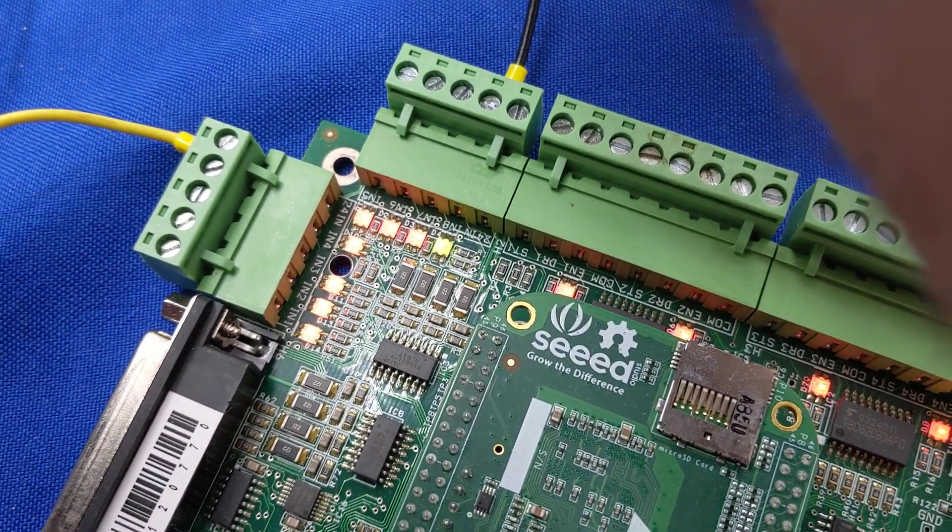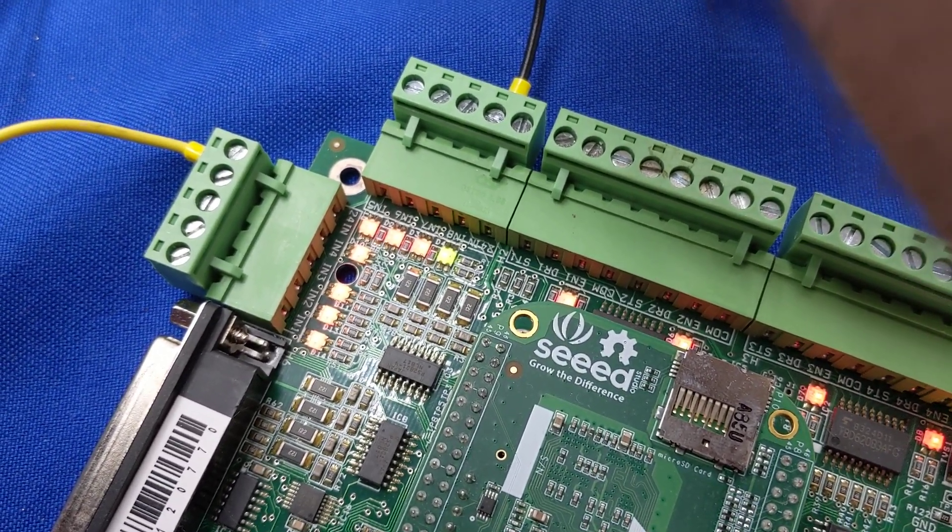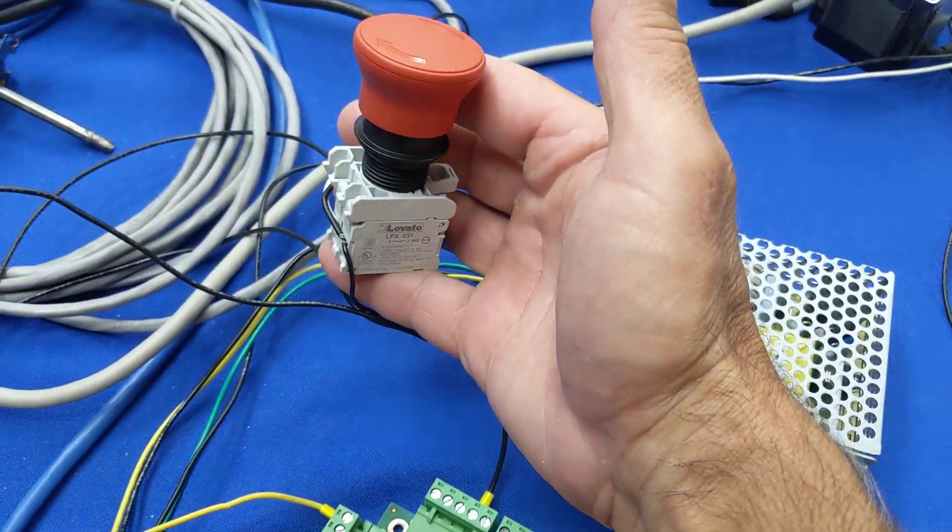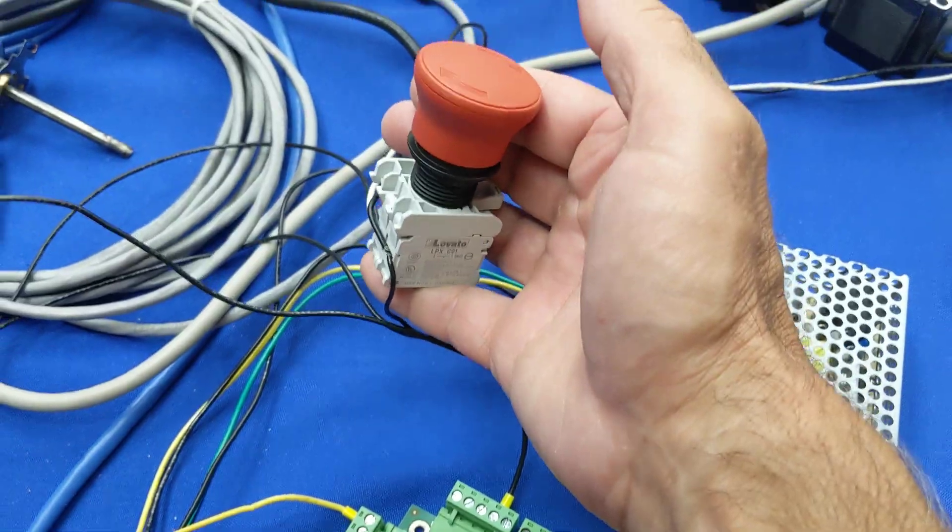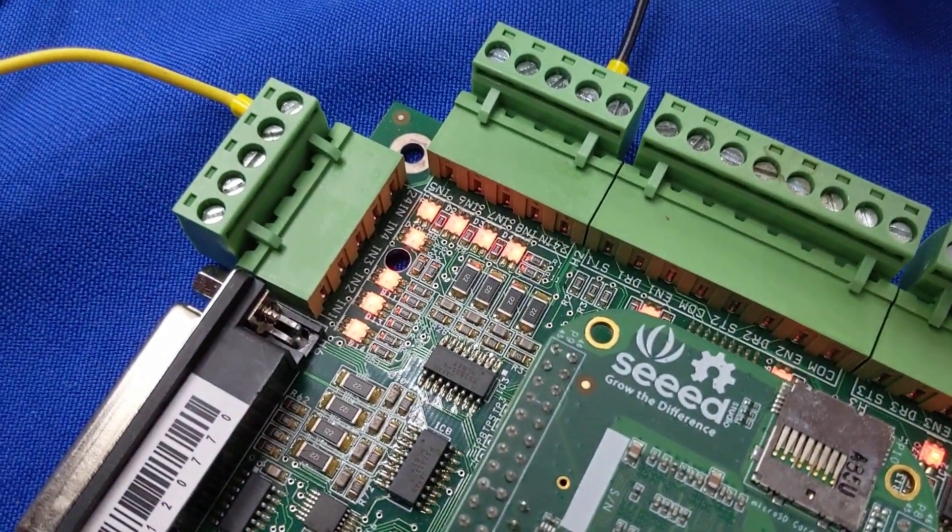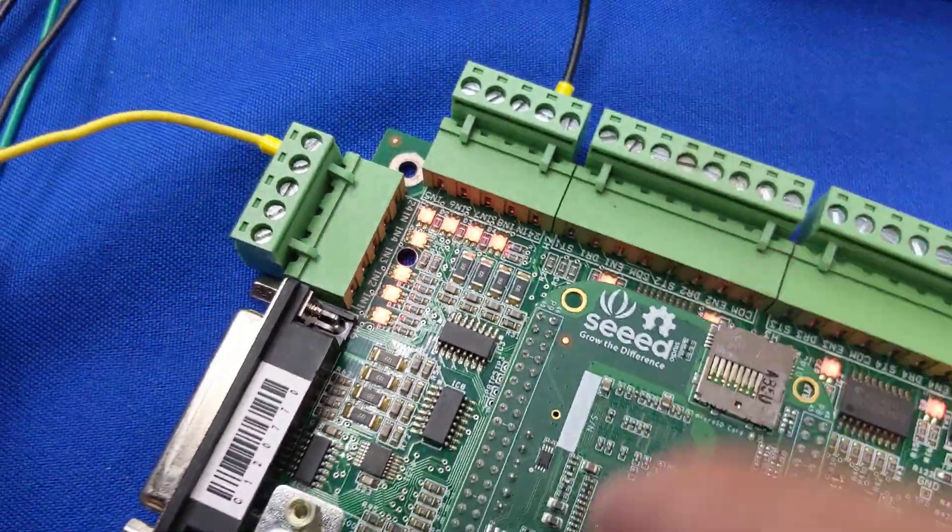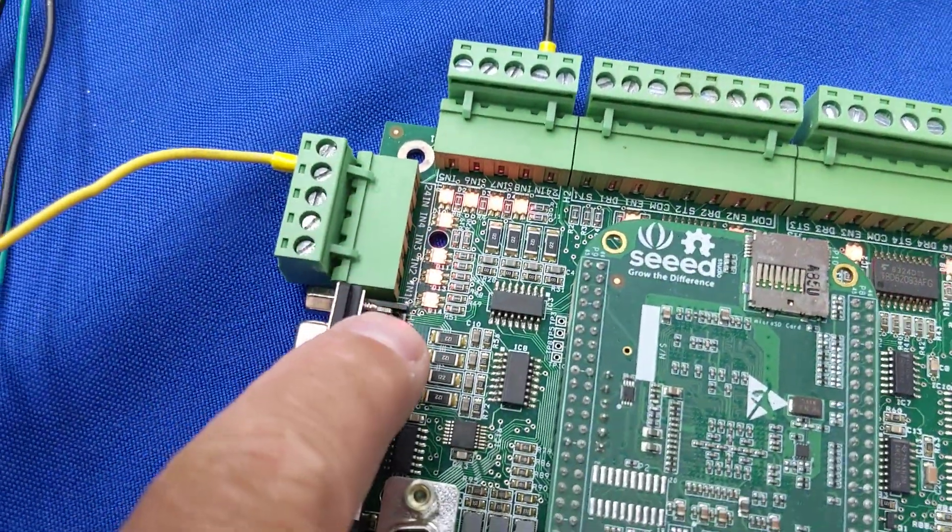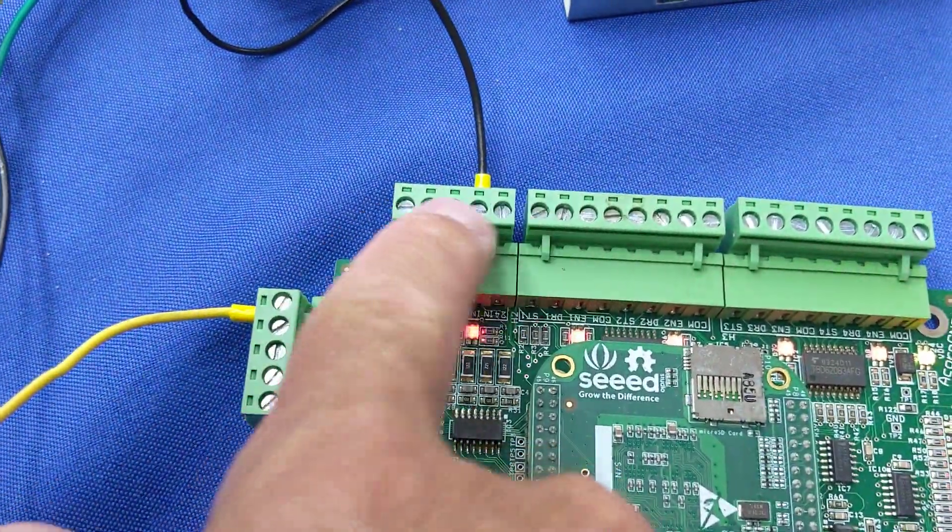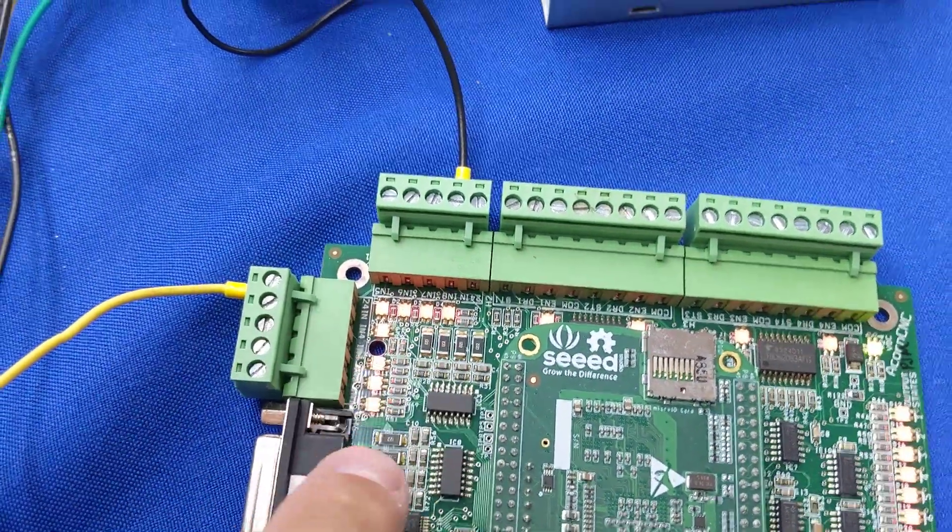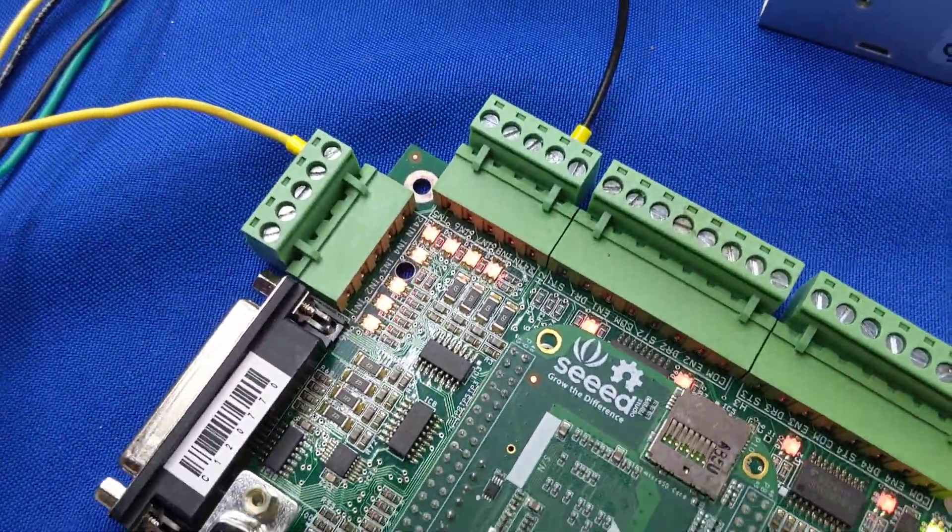So if you have a normally closed switch and it's not triggered, that's what it looks like, which is what this e-stop is. So if I push this switch, which triggers it, depresses it, it opens the circuit and the LED goes red. So all these LEDs right here are indicating that all these inputs right now are currently open. That's what red means on the inputs.